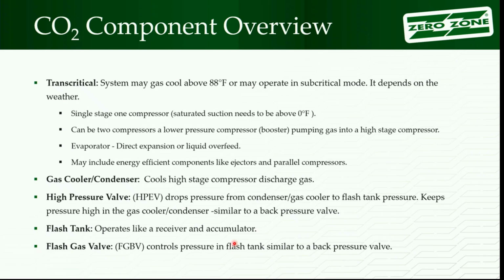But we do use the name gas cooler because when we're in transcritical mode, there's no condensation going on. If you had a sight glass on the outlet of that gas cooler and you're above 88 degrees, you won't see any liquid running on the bottom of the pipe. If there is, it's a little oil maybe, but no liquid refrigerant. You drop below 88 degrees, looking at the same sight glass, now I start seeing some liquid running, and now I'm condensing that gas. So that's where the proper name is gas cooler and then condenser, because almost everywhere in the United States it gets below 88 degrees and you turn into a condenser.